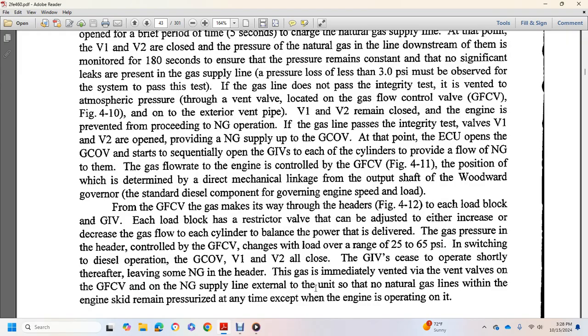The load block restrictor valve is adjusted to increase or decrease gas flow to each cylinder and balance power, with the gas delivered at header pressure. Control with the gas flow control valve changes the header pressure over a range of 25 to 65 psi. When switching to diesel operation, the gas cutout valves V1 and V2 are closed.